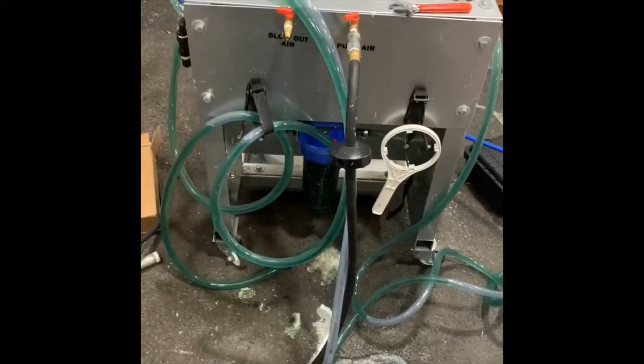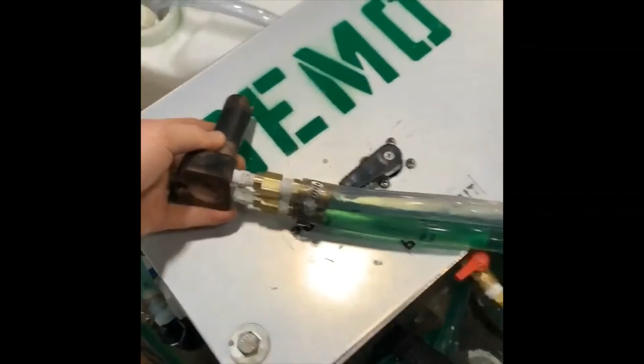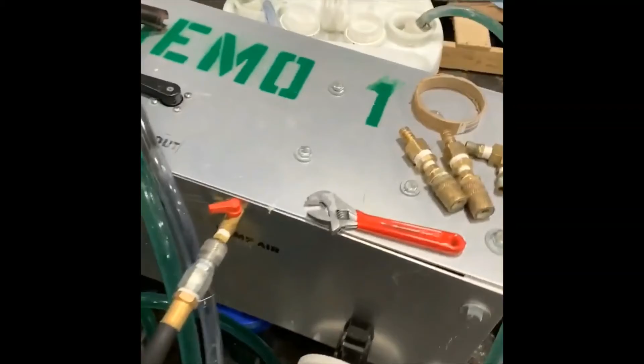One being you don't have to run an electrical line anywhere, but more importantly, the safety factor being that an air diaphragm pump will actually sense a pressure buildup if you have a blockage anywhere and pause operation, whereas most of the industry offerings have the electric pump, which can't sense that and will simply build up pressure until a line downstream ruptures, obviously causing a spill somewhere, usually a caustic solution that nobody wants.